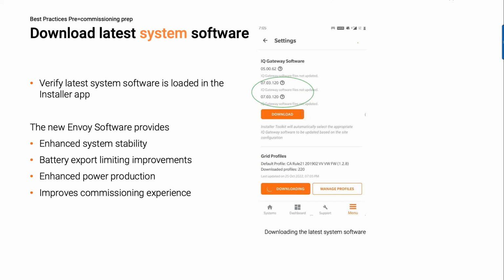What we do is we actually download all of that software into your phone. And then when you get on site and your installers are commissioning the system, the phone checks the revision of software on the system, all the different components, the batteries, IQ gateway, system controller, all of the components. It checks the software, and if that software is out of date, then it pushes an update to update those systems.